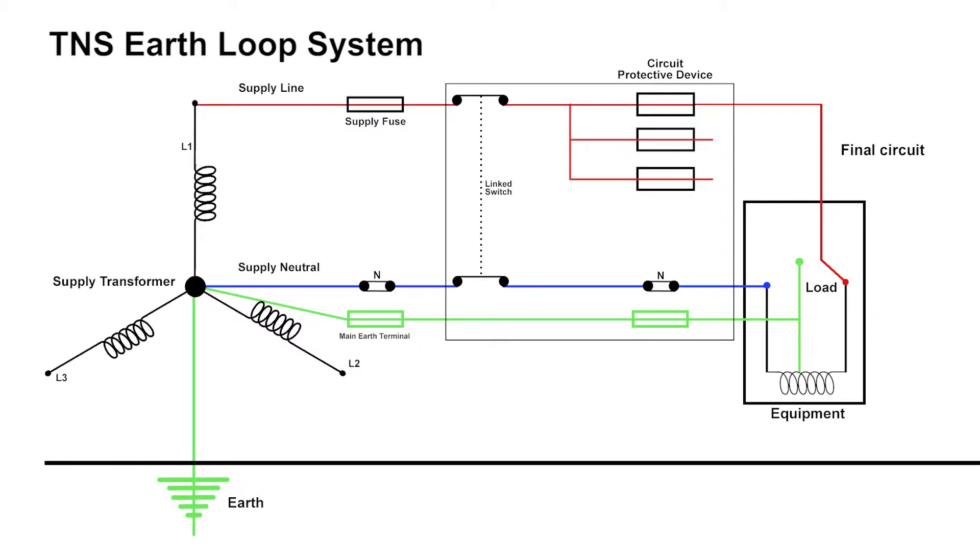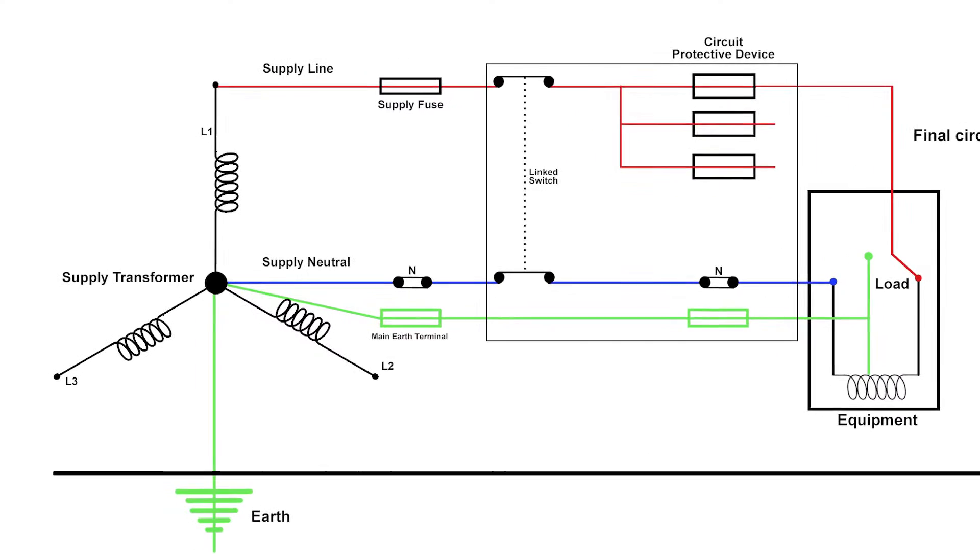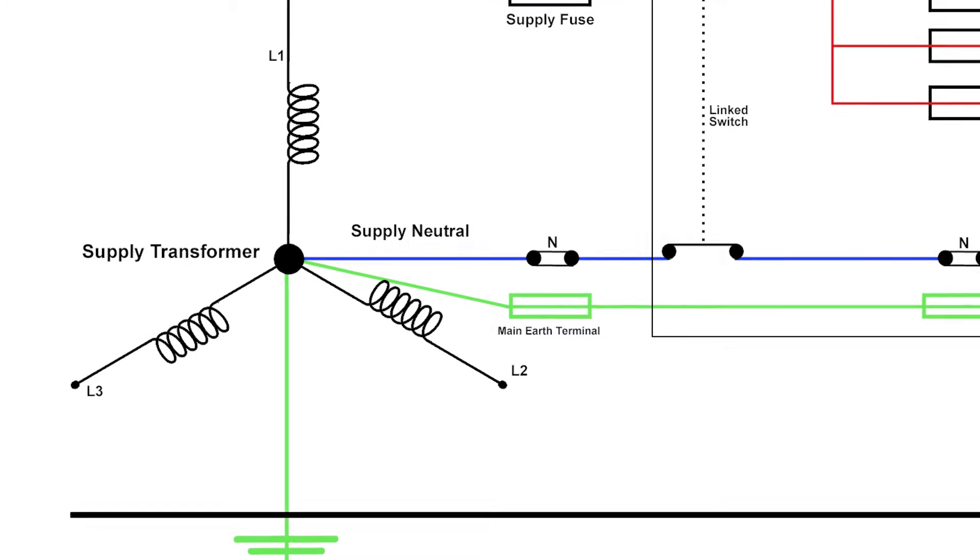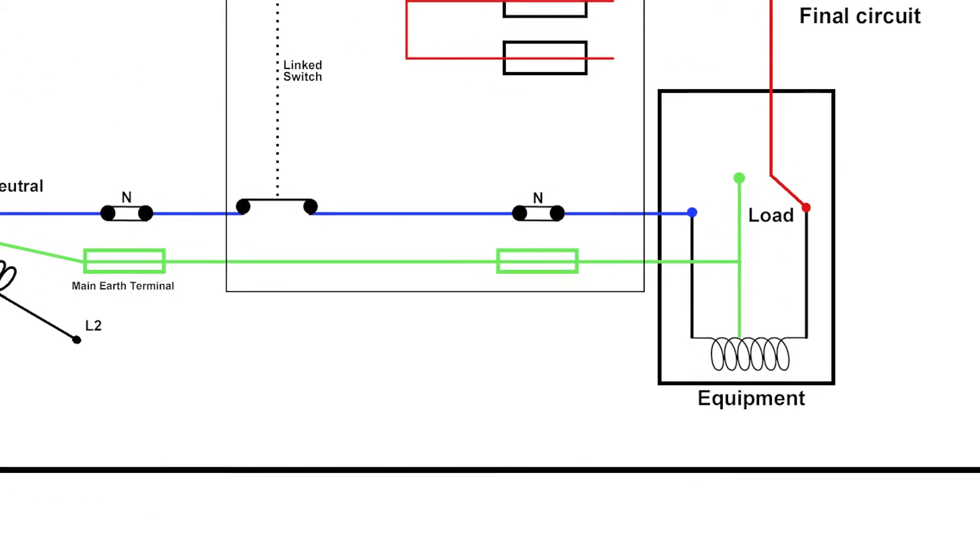The drawing we're looking at is a diagram of a TNS system. When we talk about earthing systems, the T would always stand for earth, N in this case is neutral, and S means that the neutral and the earth are entirely separate throughout the whole of the installation. In other words, they're separate from the supply transformer right through to the final circuit.